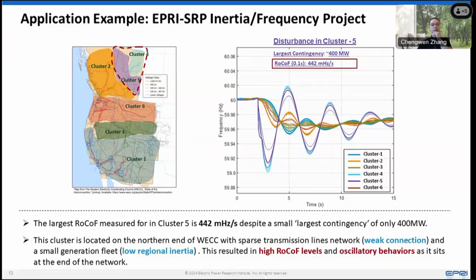It has been well known to the industry for a long time that the Alberta area in Canada can be easily excited for oscillations against the rest of the system. Also, if you have a generation disturbance in that area, the rate of change of frequency in that area tends to be large. This was also noticed by our algorithm, and we did time domain simulations to verify that.